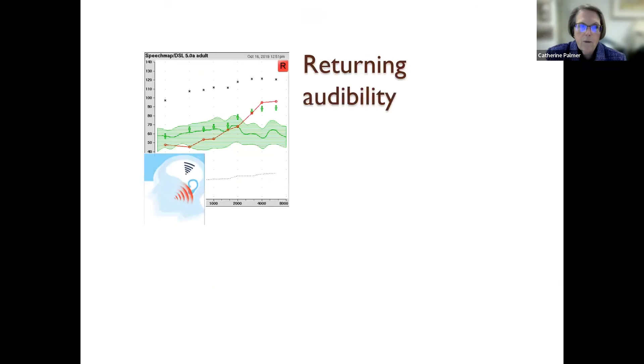So this is an example where before we've tuned the hearing aid, that dark green line is showing the output of the hearing aid. And you can see in the higher pitches to the right of the graph, it's not loud enough. It should be up by those little green plus signs. So if we do a good job tuning it, it's going to then look like this. So we've taken soft sounds and we've made them loud enough for the person to hear. And then we'll take moderate sounds and make them loud enough, but not too loud, et cetera. And that's how we fit a hearing aid.